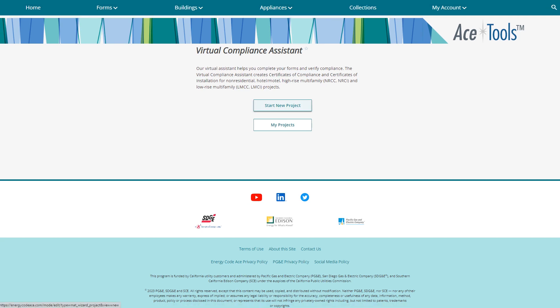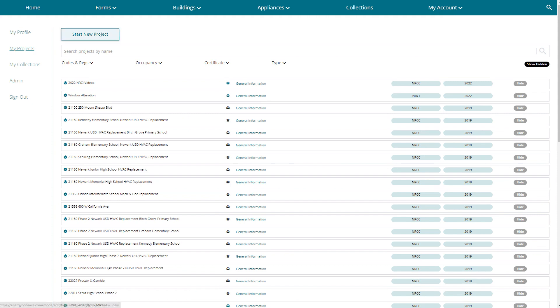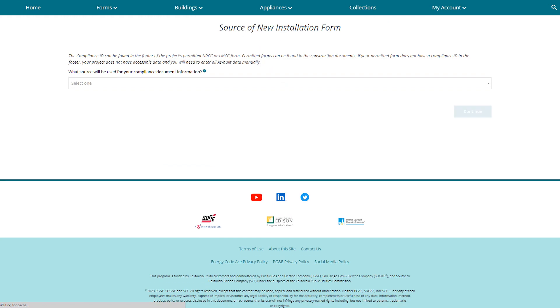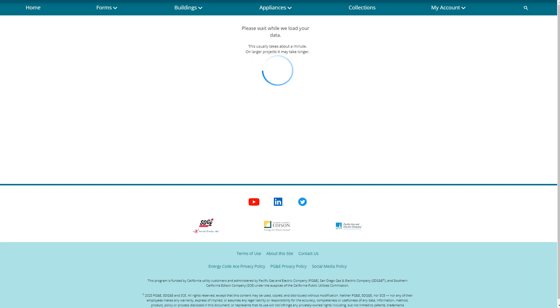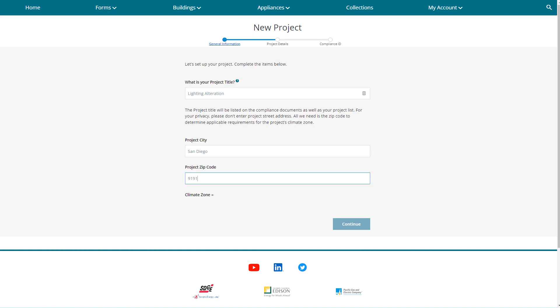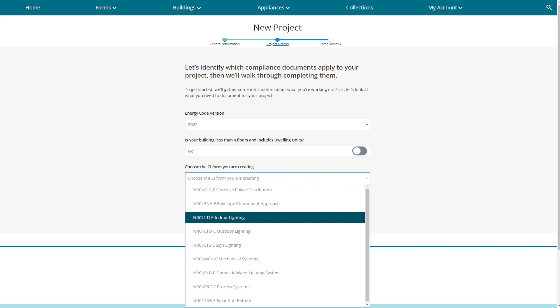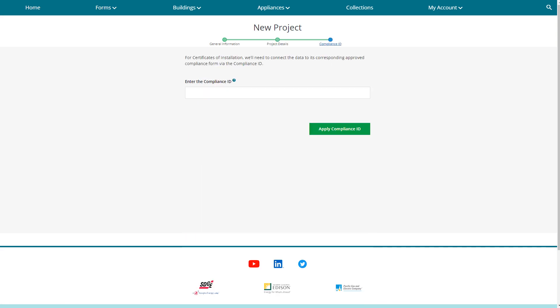You can go through Start New Projects or My Projects. Select My Projects and start a new project. Make sure to click Installation Form as the form type. Enter the compliance ID from the NRCC LTI form, and name the project however you like — project numbers, names, or addresses all work. You'll need to enter the project city and zip code; the zip code helps the VCA identify the appropriate climate zone. Select the 2022 code cycle and document the LTI form, then enter the compliance ID including the dashes from the lower right-hand corner of the Certificate of Compliance Form.